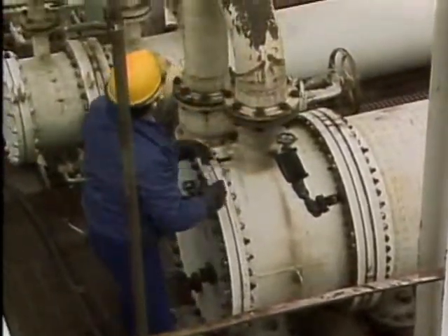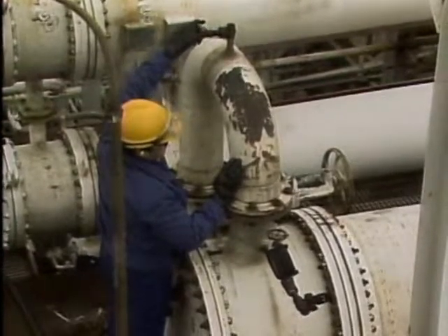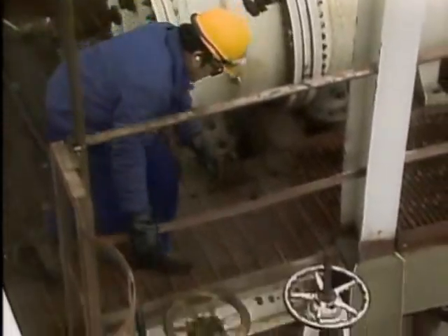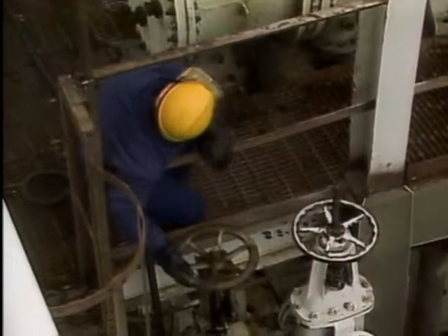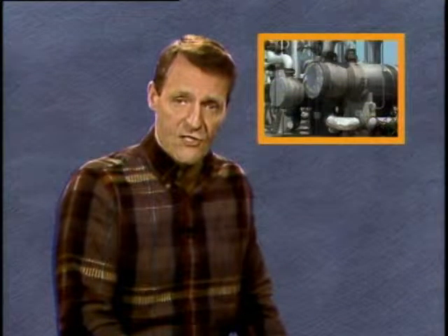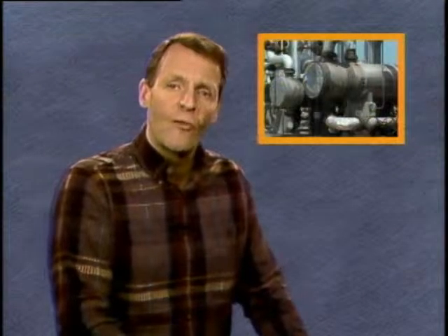Regardless of how gases get into the heat exchanger, the unit must be vented to allow them to escape. Repeated venting may be necessary to ensure that the heat exchanger remains free of air and other undesirable gases. However, excessive venting can cause its own problems. For example, each venting may allow a small amount of the process fluid to be lost from the process. This reduces the efficiency of the process. Venting may be only a temporary fix. If the source of the gas is the process, there may be a problem with the process or with one of the components in the process.